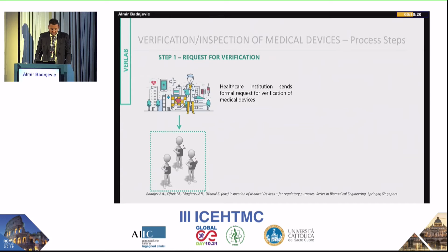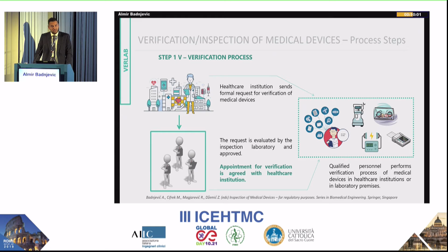What are the steps for a request for verification or inspection? First, the healthcare institution sends a formal request for verification of medical devices. Then the request is evaluated and checked to see whether it is really in accordance with the legal metrology rules for medical devices. If the answer is yes, they send people to measure those devices, and then we get the first results.